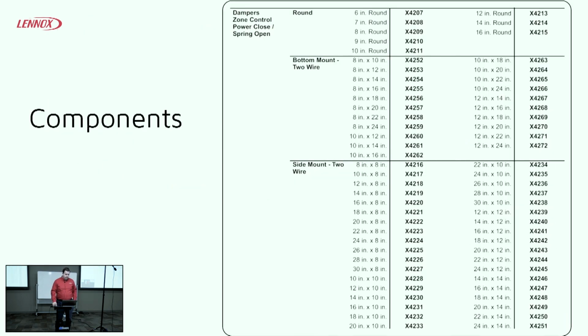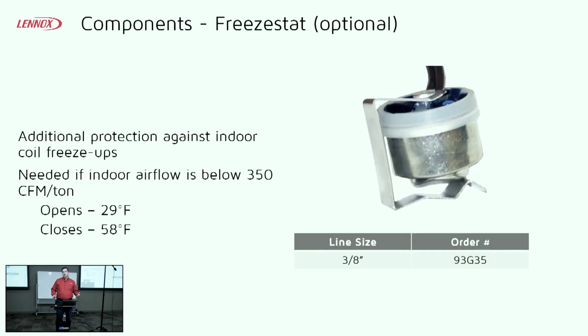Of course, something else out of the application guideline gives us all the different dampers that we provide, either round or square, and they have the bottom mount and the side mount on here. That's where the damper motor is, always going to be on that. Basically, on the bottom mount, the motor's on the long side of the square damper. On the side mount, it's on the short side.